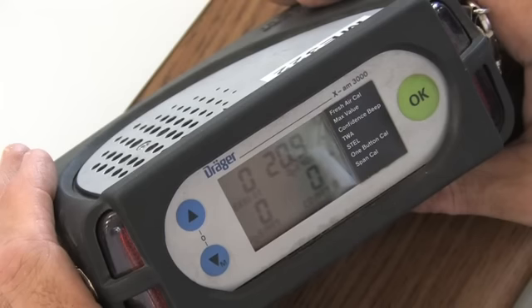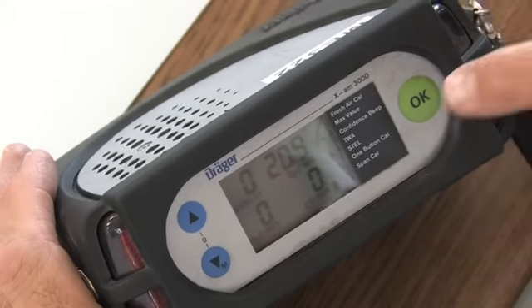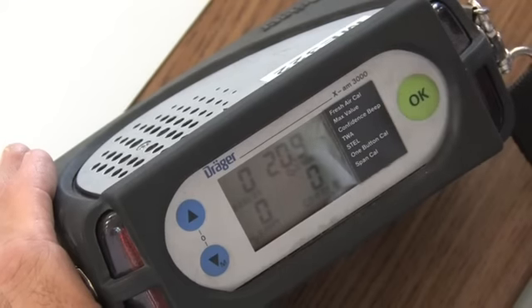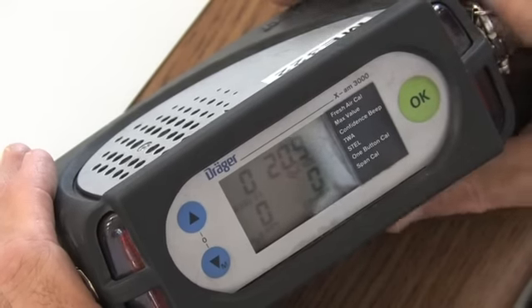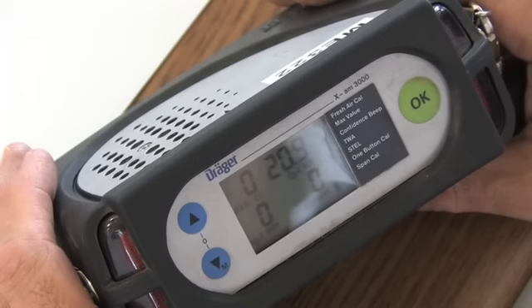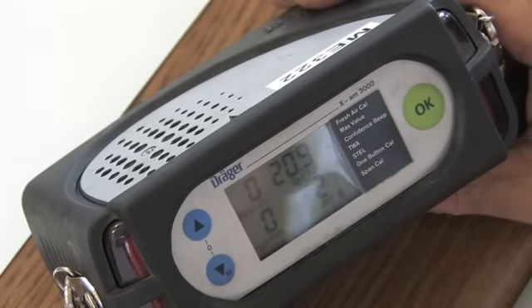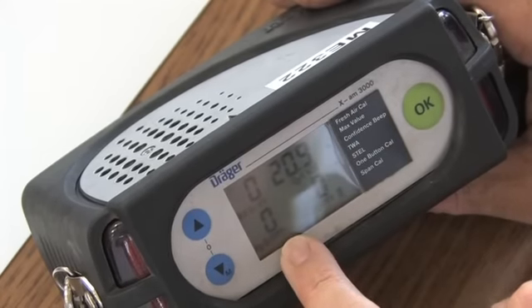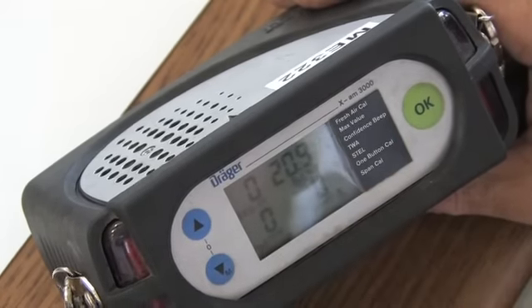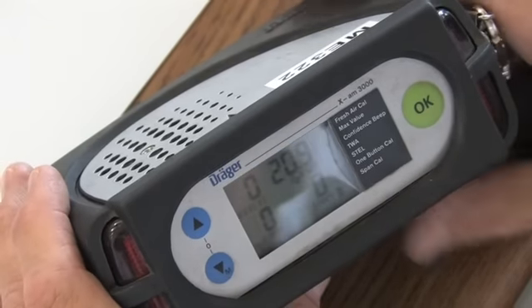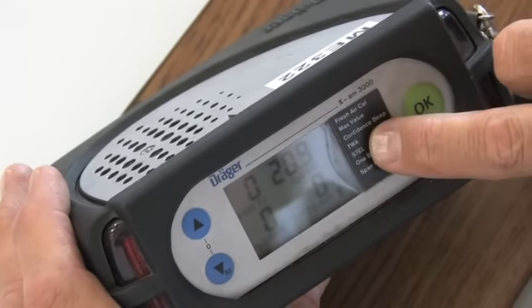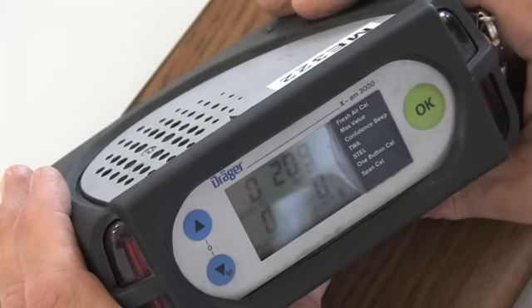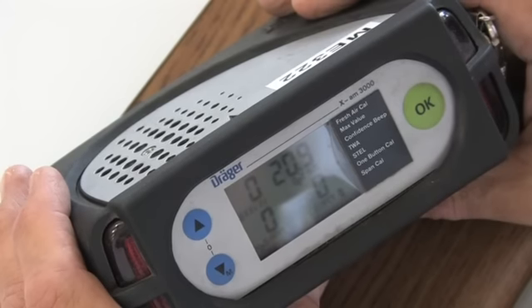You also heard a confidence beep just there a minute ago because we have an arrow pointing to it. That can only be removed through CC Vision with a computer. Oxygen percent volume 20.9, H2S is ppm 0, CO ppm 0. Also the short-term exposure level is also on, and that can be turned off as well.